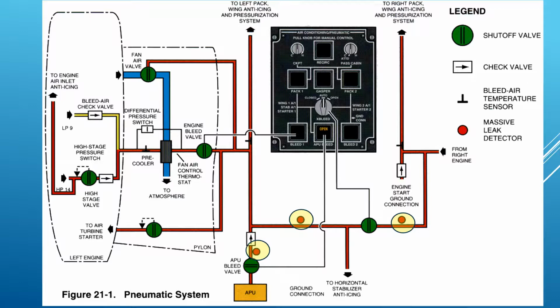Well, it's a high stage pressure switch. So we're going to base whether the high stage valve is open or closed based on the pressure coming off the 14th stage air. If the 14th stage air pressure is less than 46 psi, that means 9th stage air is even lower, and we're going to use it. We're going to use 14th stage air.